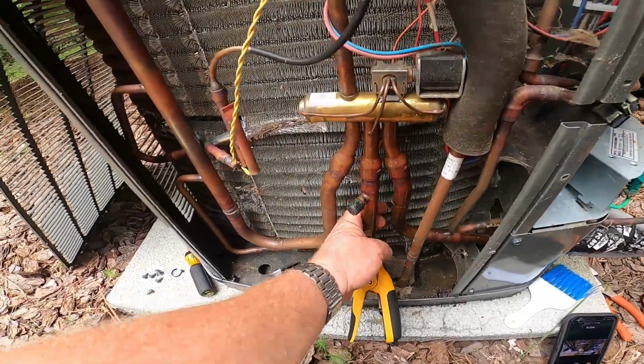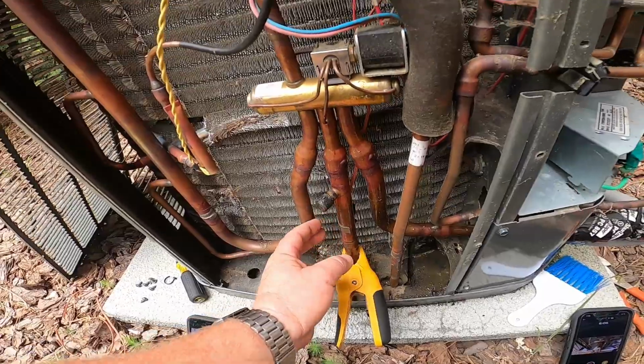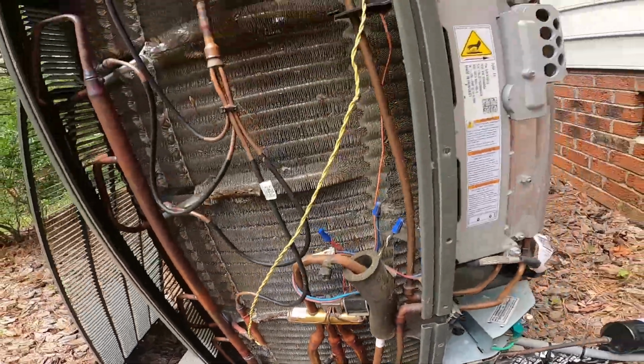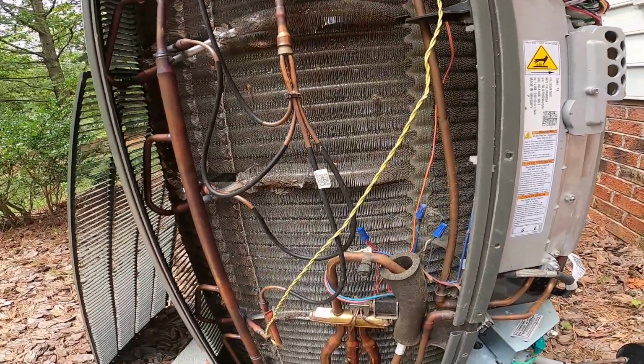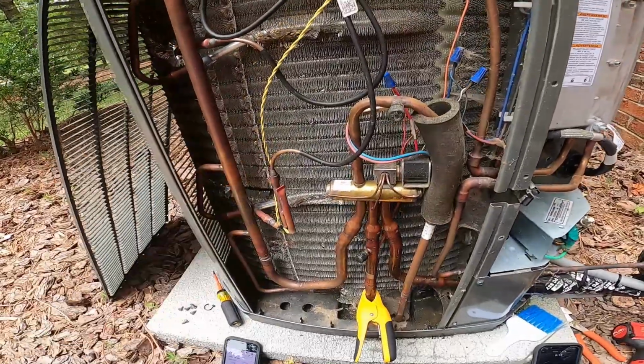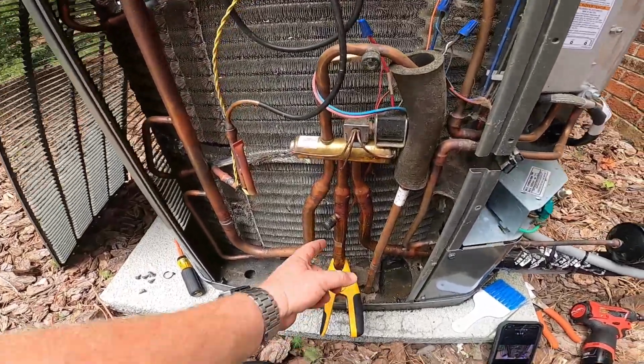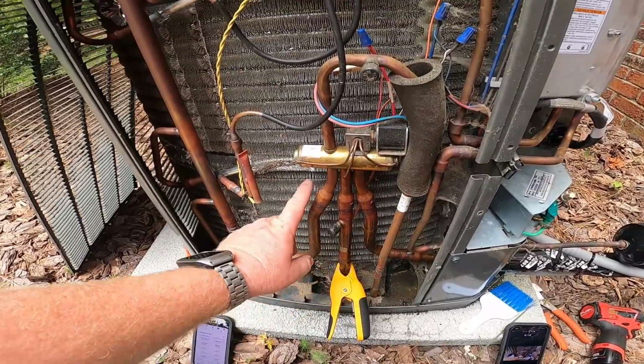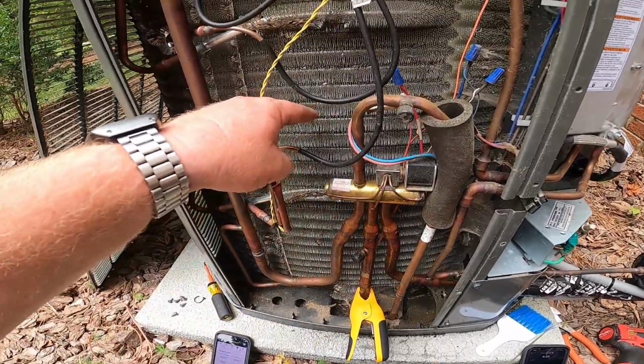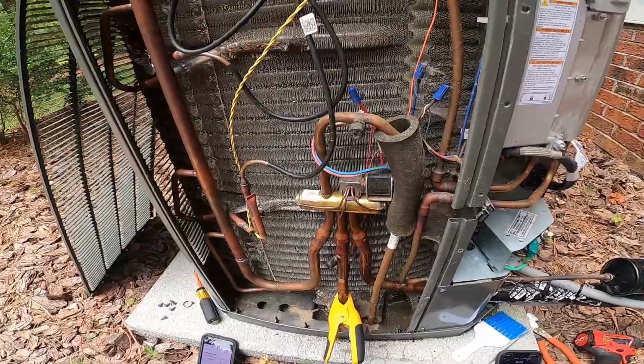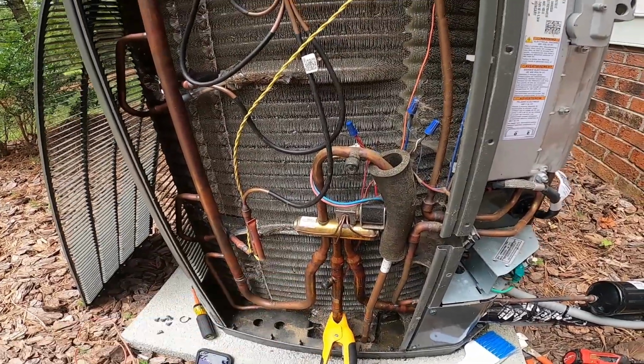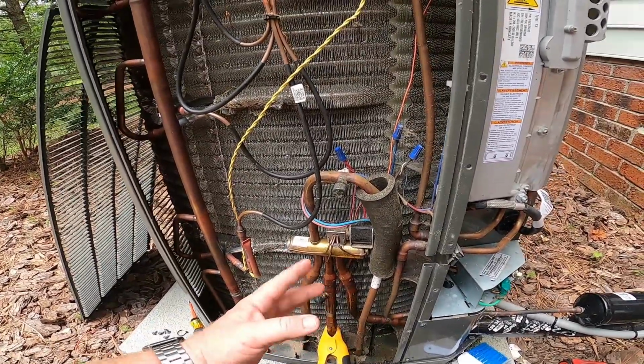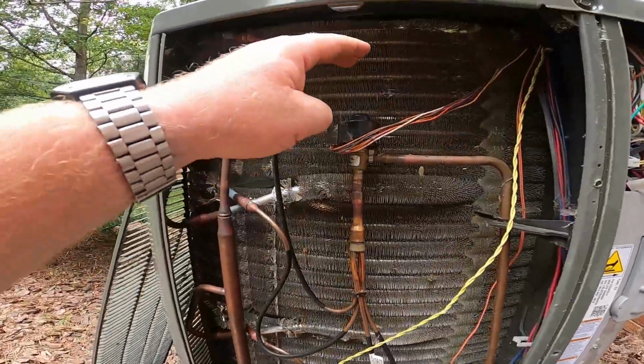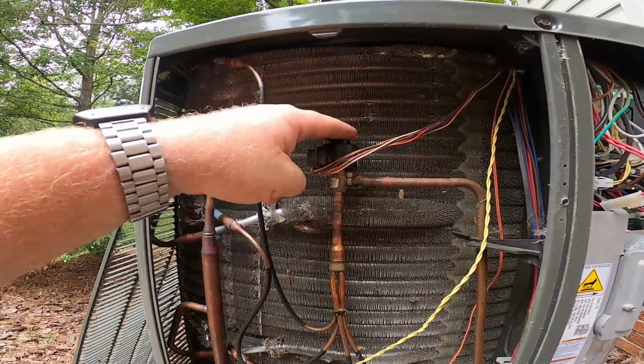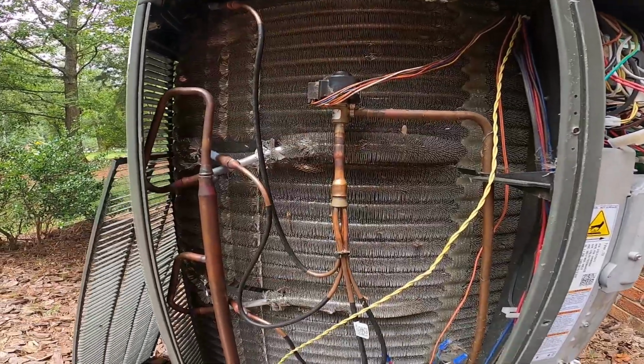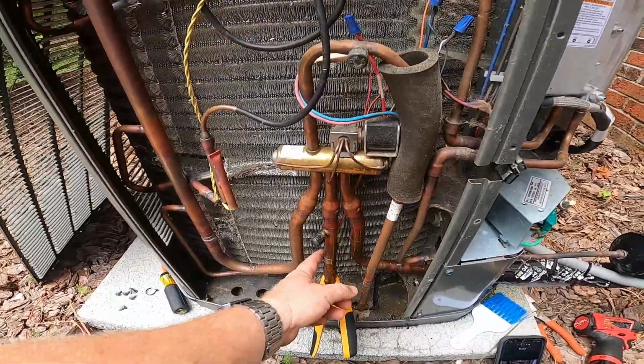So, like I was explaining to him, and you missed it, this is just going to measure your superheat on this outdoor coil when you are running this thing in heat mode. If it reads out of range, it'll still give a fault. But in heat mode, it's going to read the suction line temperature. You've got a pressure transducer back inside the unit connected to the suction line off the coil or off the compressor, and then it's going to measure the superheat and throttle this outdoor EEV in heat mode to regulate that refrigerant flow. So that's the reason I was explaining to him.